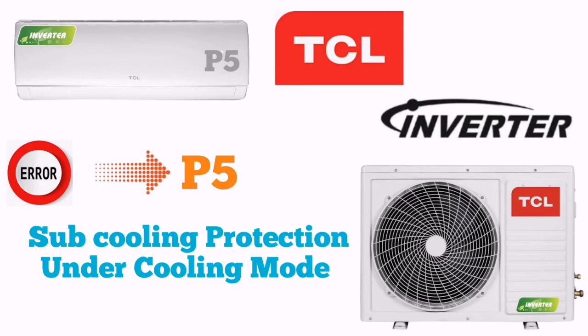When you see error P5, it means subcooling protection or undercooling protection. It means our indoor unit is not clean, same as the P4 error shows in our outdoor unit. Sometimes if our indoor unit filter is totally blocked and our fan blower is also totally blocked, it can show error P5. When you see the indoor is totally clean and it is showing the same error, then you have to check your room temperature sensor and your indoor coil sensor.